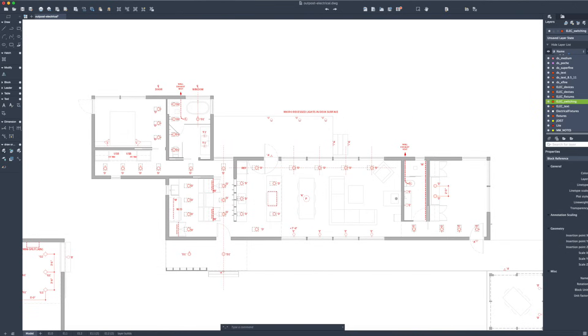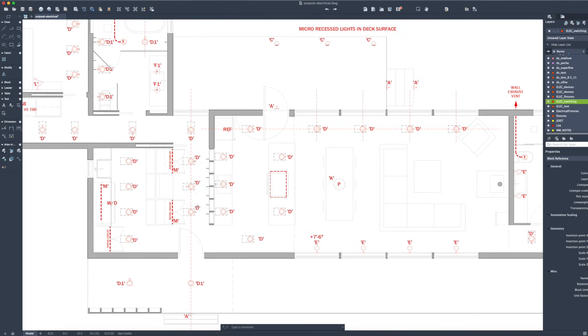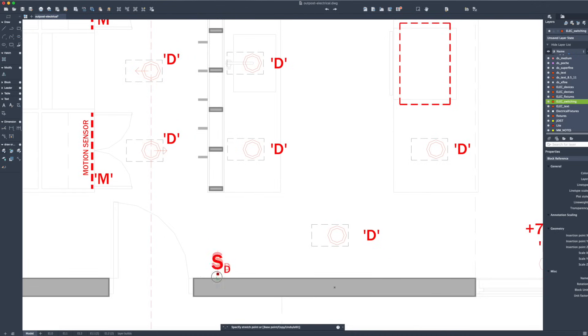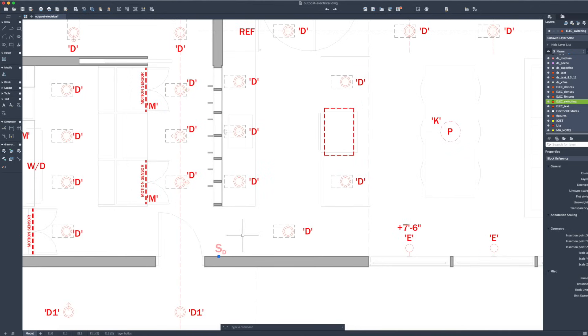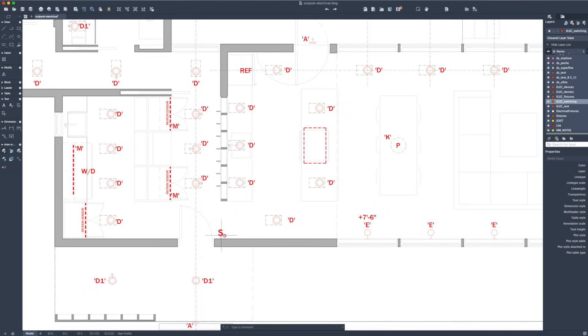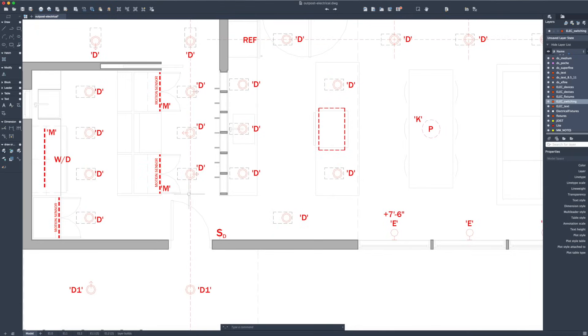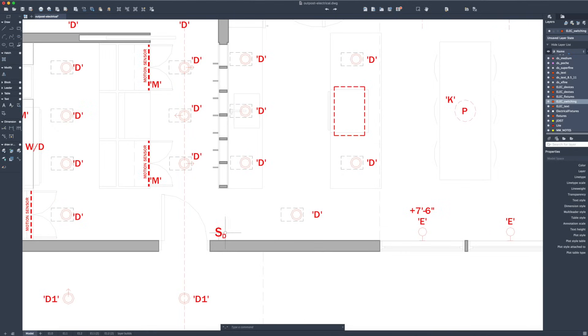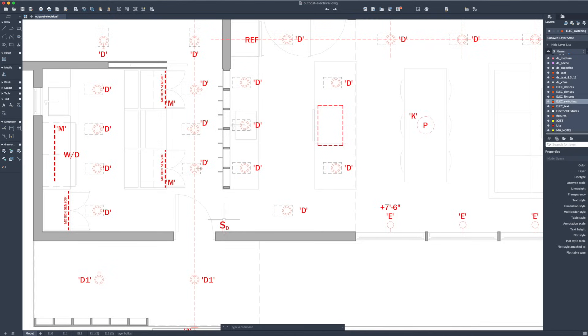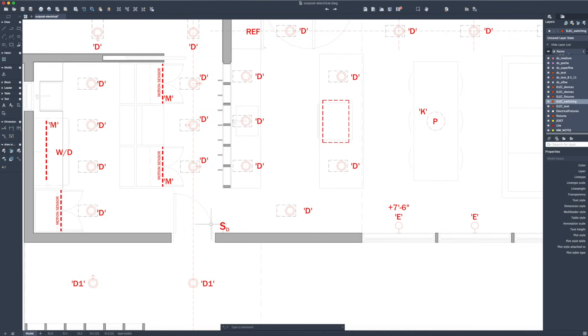Once I've completed that, I'll start working on my circuiting. Circuiting is just defining which lights are switched on together. Here you'll see my block indication for a dimmer switch. I don't call out three-way or four-way switches — it leads to confusion. If you decide to change the number of switches and forget to change the designation from three-way to four-way, that can be an opening for a change order. So I just leave it up to the electrician to determine whether a switch is a three-way, four-way, or just a single switch.